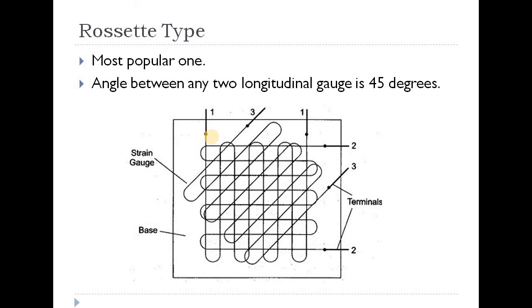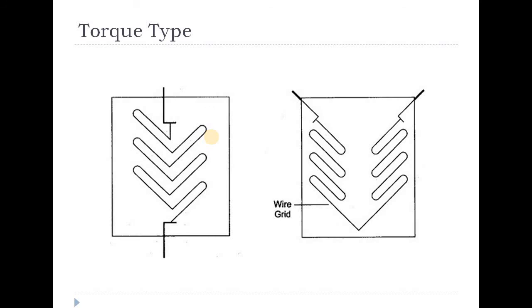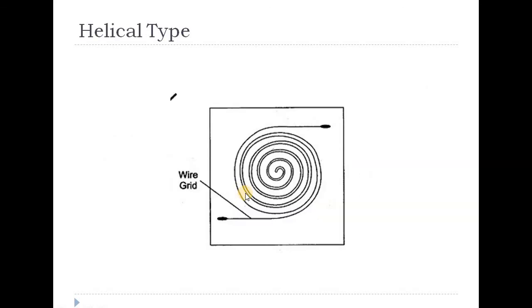The angle between any two longitudinal gauges is 45 degrees — this makes the rosette type the most popular. The third type is torque type, which uses a wire grid arrangement suitable for torque measurement. The last one is helical type — not a rotatory type but a helical arrangement.